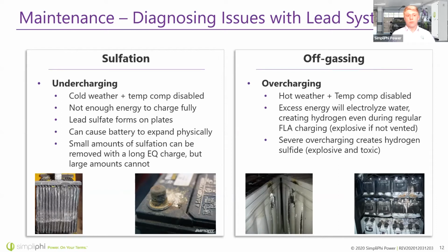Sulfation happens when there is undercharging—if the lead acid battery remains at a partial state of charge for a long time and doesn't receive a full charge often, it will sulfate. This definitely impacts battery performance, and in the long run a lot of sulfation can completely destroy your battery, even causing it to physically expand. Small amounts of sulfation can often be removed with a very long, controlled EQ charge, but large amounts definitely cannot be removed.